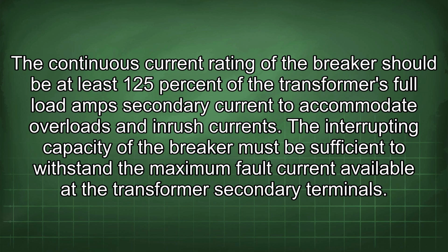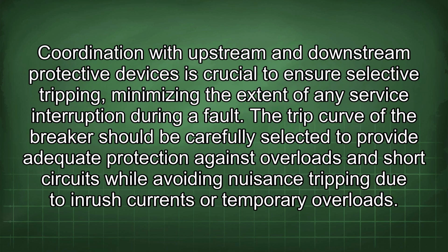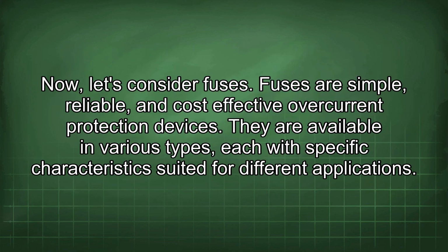The interrupting capacity of the breaker must be sufficient to withstand the maximum fault current available at the transformer secondary terminals. Coordination with upstream and downstream protective devices is crucial to ensure selective tripping, minimizing the extent of any service interruption during a fault. The trip curve of the breaker should be carefully selected to provide adequate protection against overloads and short circuits while avoiding nuisance tripping due to inrush currents or temporary overloads. Now, let's consider fuses.